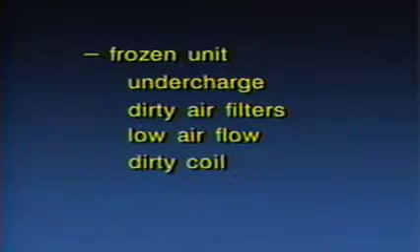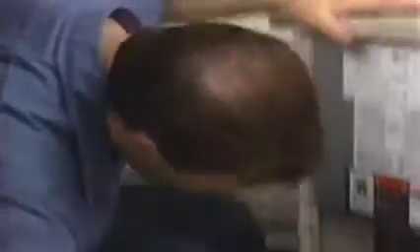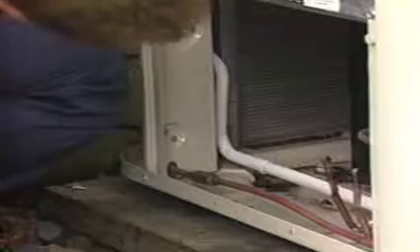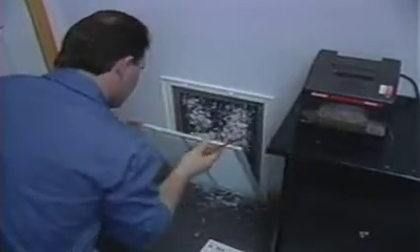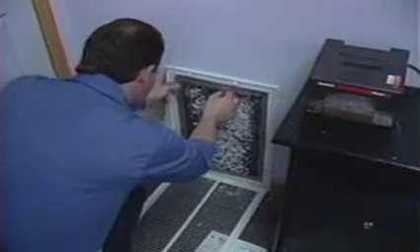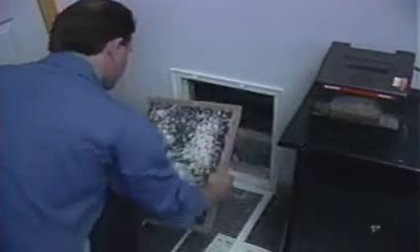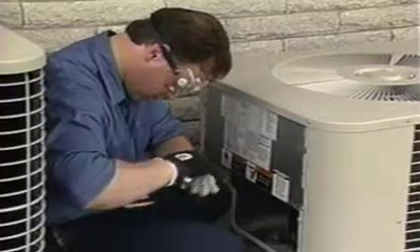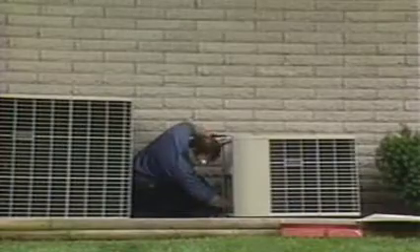Let's take a moment to review the facts. The unit was frozen. This could have been caused by undercharge, dirty air filters, low airflow, a dirty coil, or a defective metering device. The first step was to thaw the unit while looking for the problem. While the unit thawed, restricted filters were found and replaced. Since the filters were dirty, the technician suspected correctly that the coil was also dirty. After thawing the coil, the next step was to start the unit. Note that the line leaving the metering device was extremely cold — do not make the mistake of thinking undercharge. We have determined that the refrigerant is not boiling to a vapor in the coil, and the technician noted that the coil and fan are dirty.